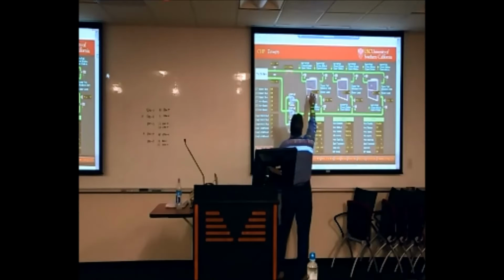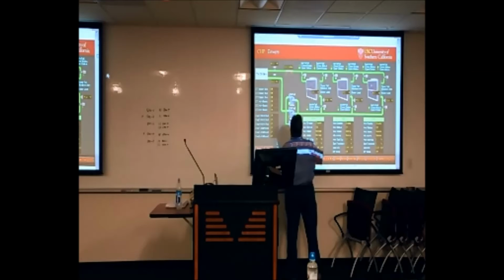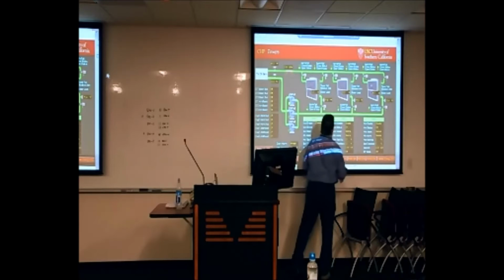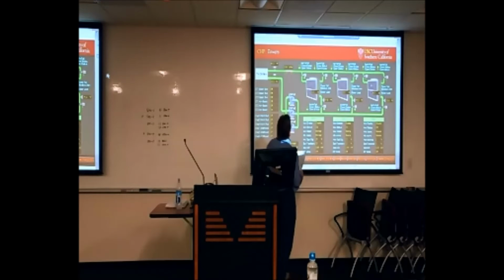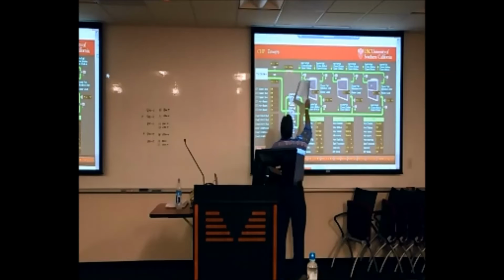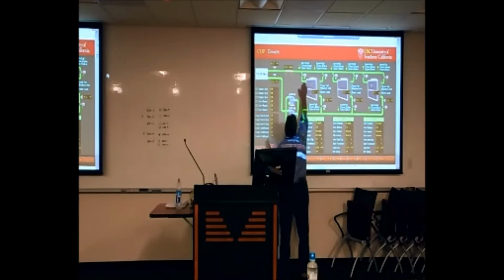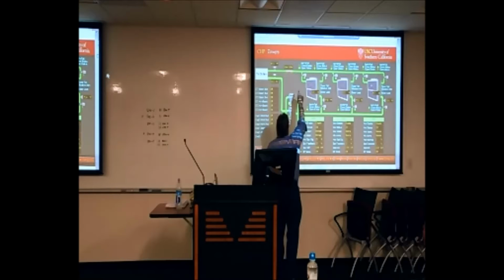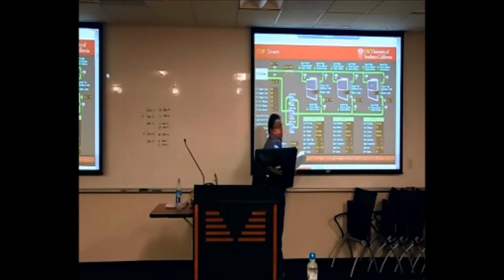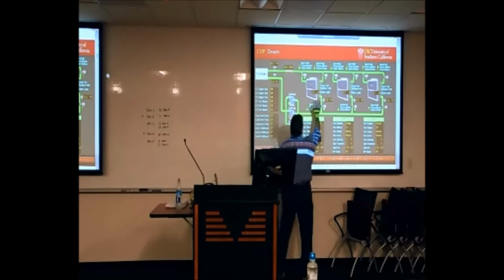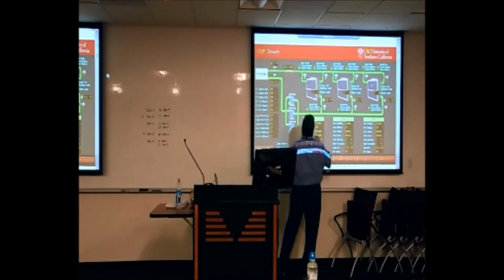So up on the top of the tower, there's a bray valve on the top of each tower for the fill on each side of the tower. And then beneath the tower, there's a leaving valve for each tower. So each tower does have 3 isolation valves associated with it. And for each valve, we have the open command, which is right here at the valve, the little indication of a valve actuator. And then we've got the open and close status for each valve, and then a failure indication for each valve. So associated with each valve is that open close status, that failure indication, as well as the command for the valve right here.